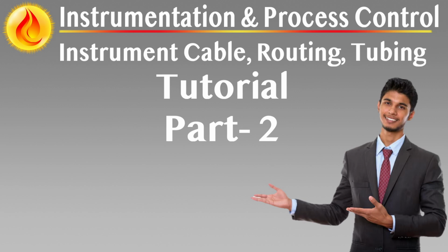Screens within control room or auxiliary system cabling must also be connected to instrument earth at the MDF only. Where screened cables connect two MDFs or two instrument cabinets, the screen must be bonded at only one end to maintain the star configuration and minimize circulating current risk.